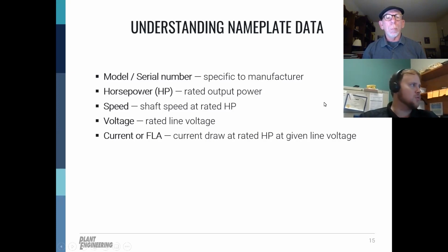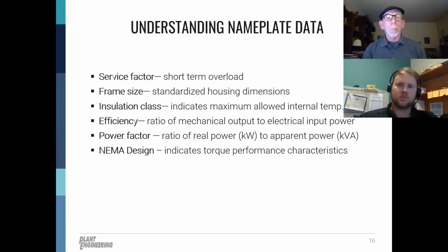So on the next slide, we've got a few more of the nameplate parameters. Listed first, service factor. That's the short-term overload factor. Also frame size. Frame size is something that's standardized across the industry. Insulation class, that indicates the maximum allowable internal temperature of the machine. You also have full load running efficiency, power factor. That's the ratio of real power that you're actually using by the machine to total power, which would be generated by your power utility. And then lastly, NEMA design letter.